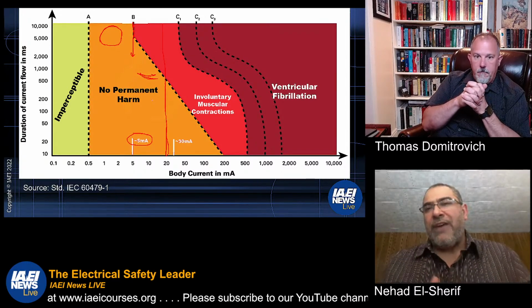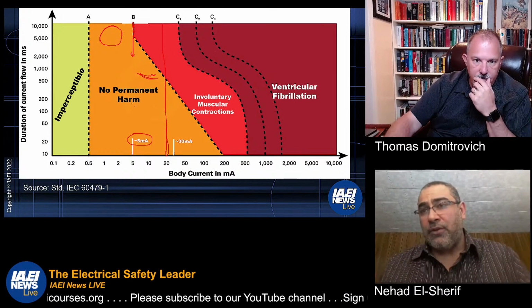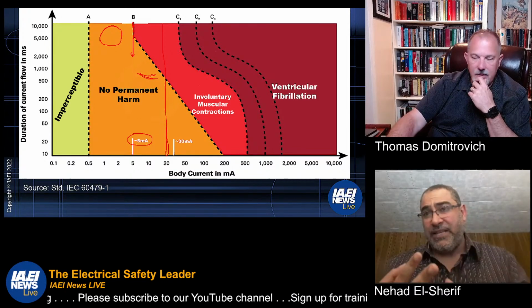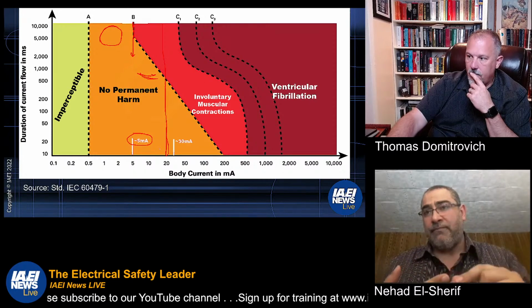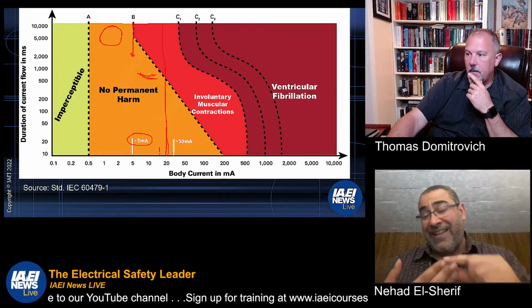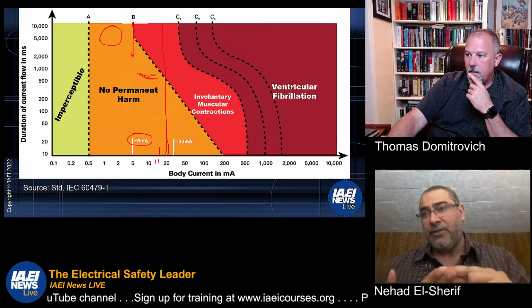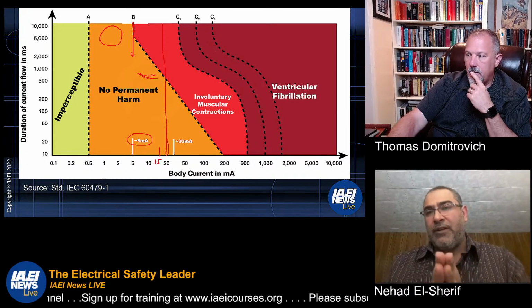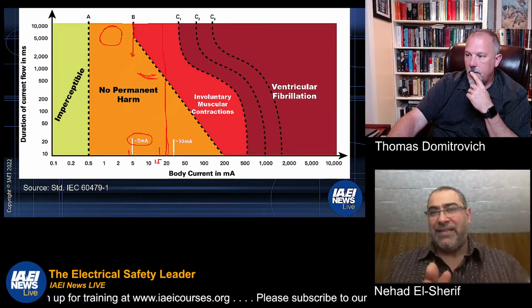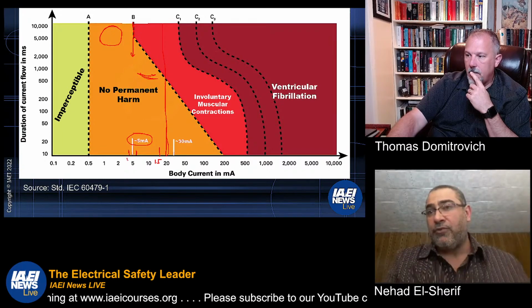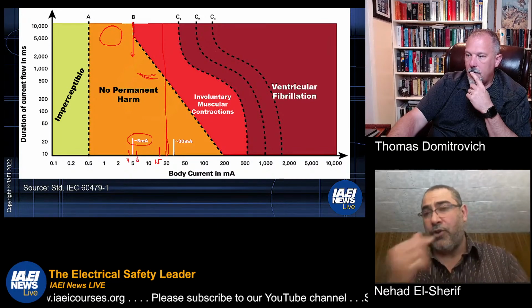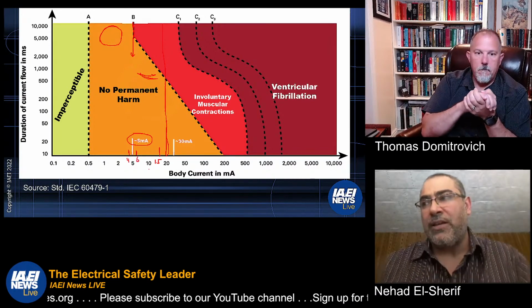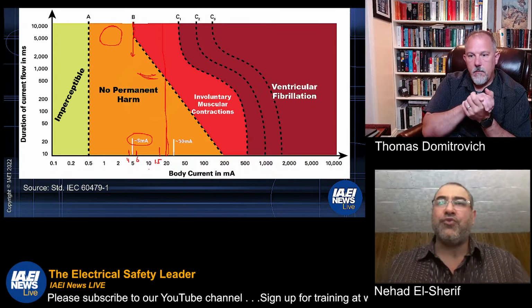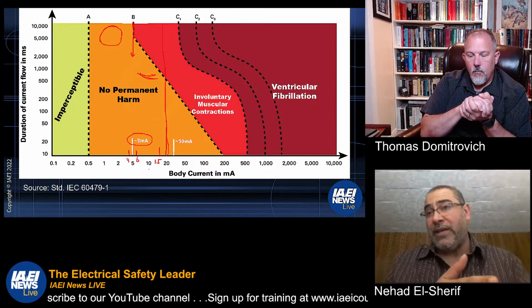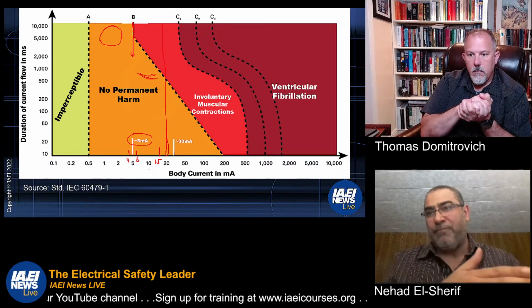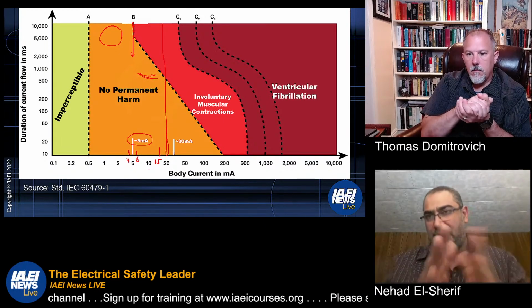But when you have a 20 milliamp or higher ground fault and you install Class A, Class C, Class D, all of them will trip at the same time if they are certified or listed and meet your requirements, because it's the same equation. Like Tom said, the only difference is if you have any ground fault between 6 and 20, then Class A would trip, but Class C, D will not trip. And in the standard, UL gives an option for manufacturers to design a Class C that can trip lower than the 15 milliamp, maybe at the 6 milliamp as well, like only Class C.